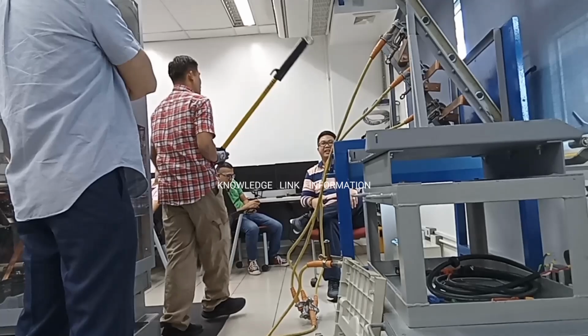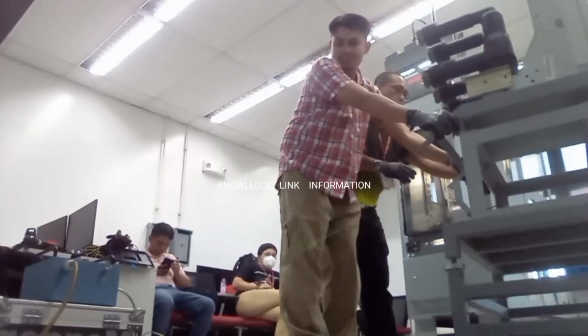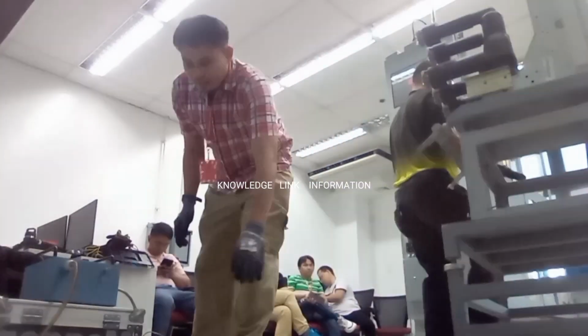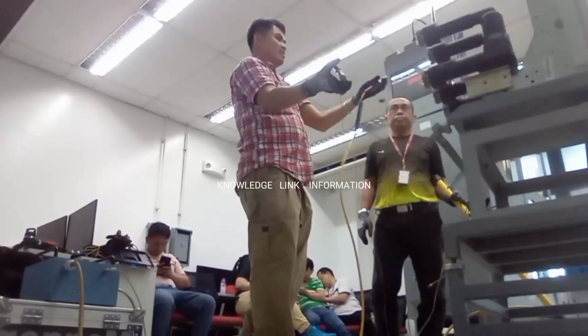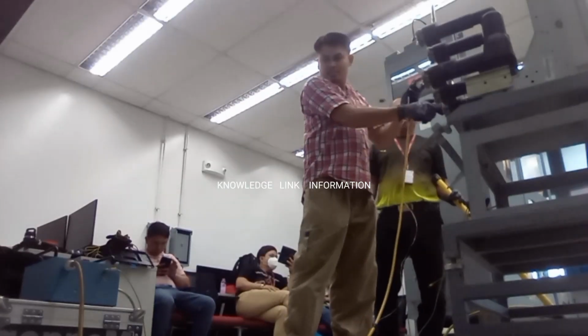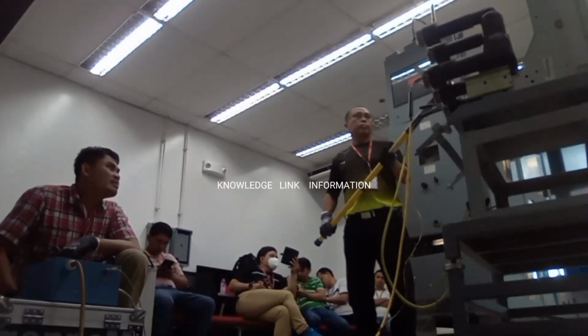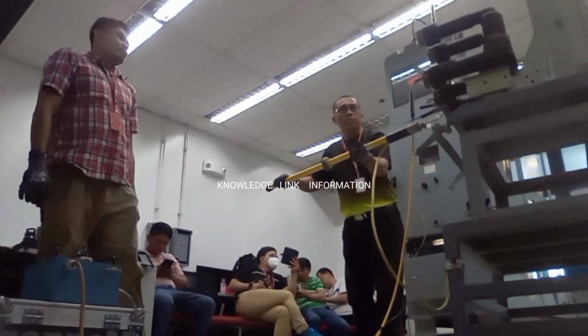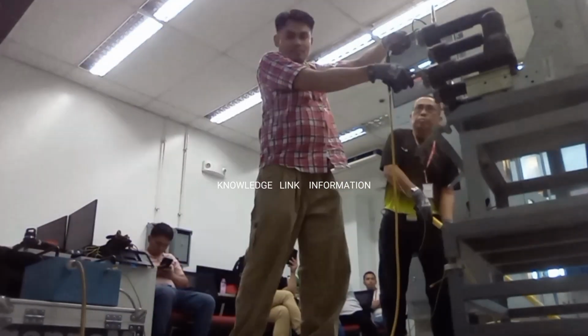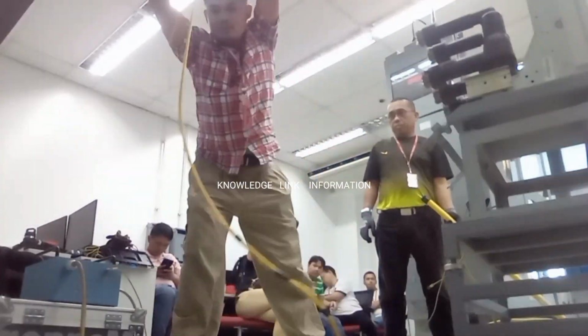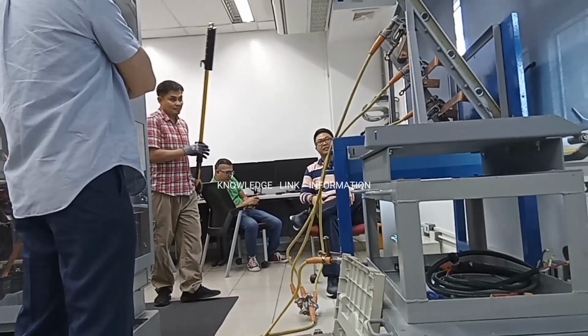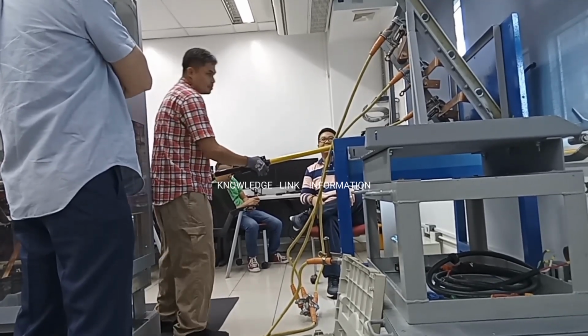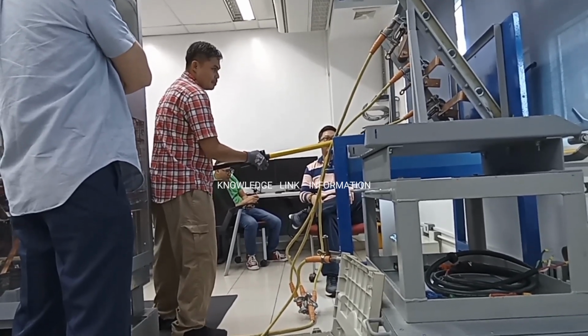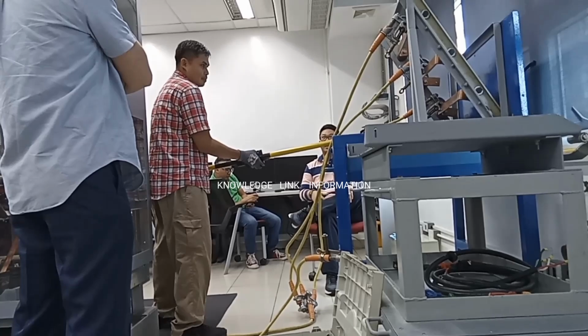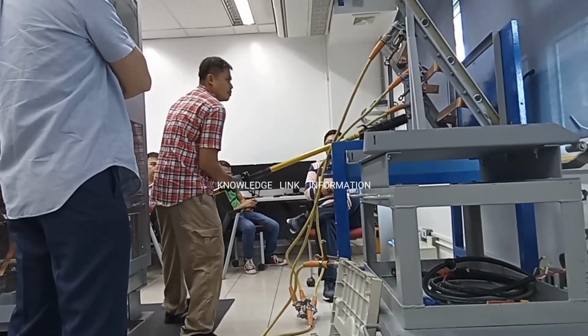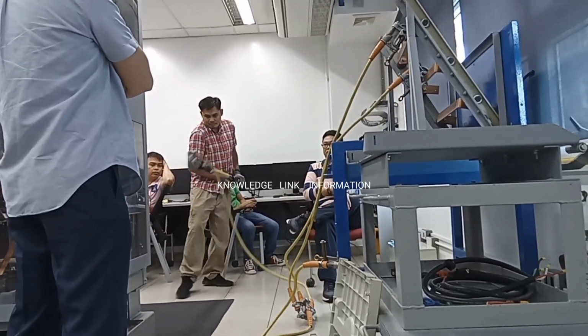Number 18. We are now safe to do any high-voltage job. It is strongly recommended that a minimum of 2 persons always do the high-voltage job for safety reasons, so that they can call for help if something goes wrong. Number 19. Go back to the bus bar earthing connection when we have finished all the high-voltage job, and remove the connection clamp on the first phase.